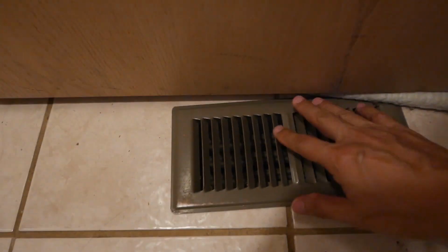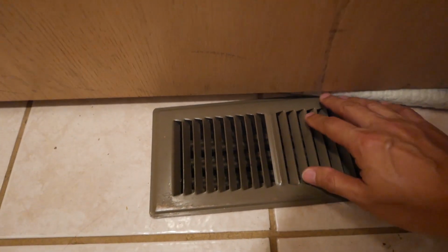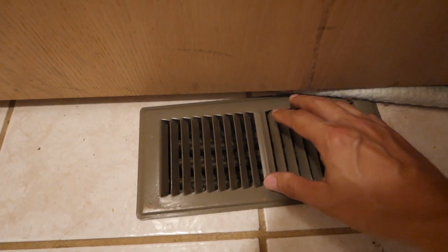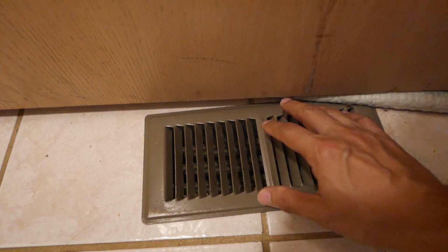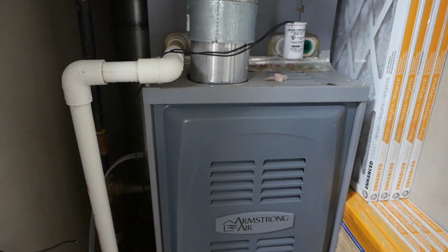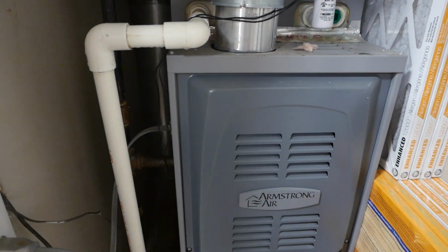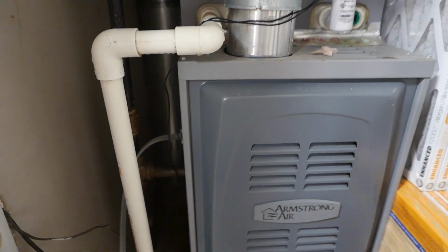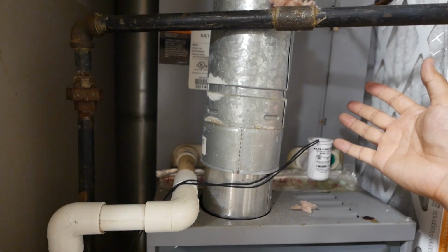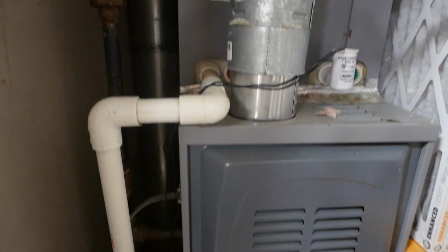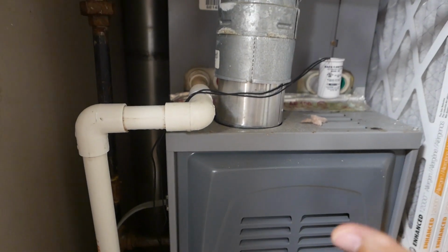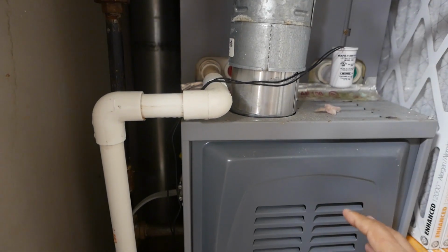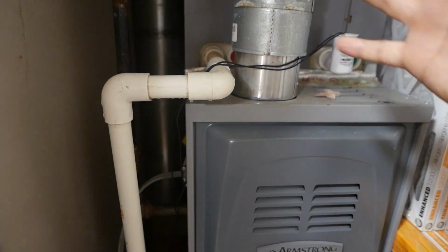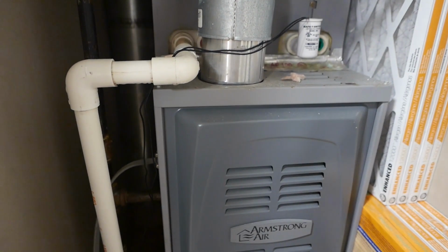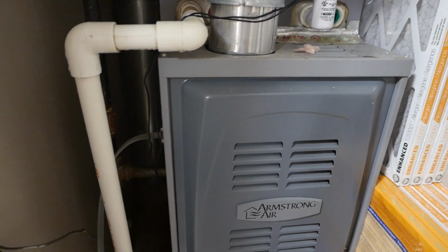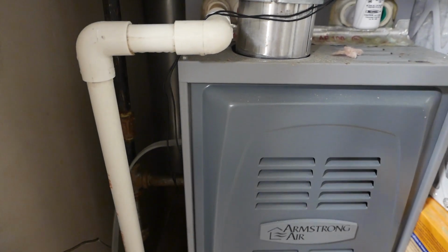So when I get to the air vents, I can feel that the air is just lukewarm. Right here is the air handler, and at the air handler unit you can hear the fan running, so it's getting the right signal to turn on the fan, but the air is not cool. So let's go check outside at the condensing unit.